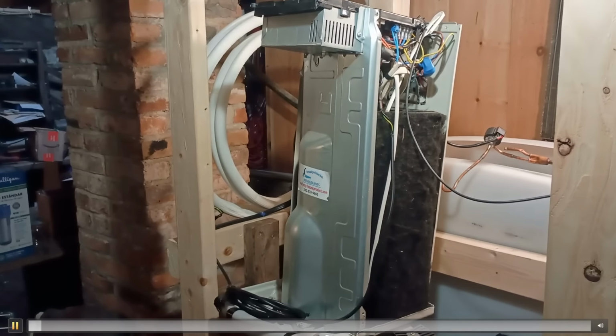And if you keep dropping the temperature to like 0 degrees Fahrenheit, now the COP is 2, which means half the heat energy is coming from electric and half is coming from the ground, where at 3 it's 1/3 of the energy coming from electricity and 2/3 coming from the ground. So it's a major hit.